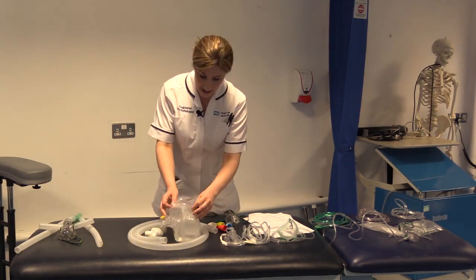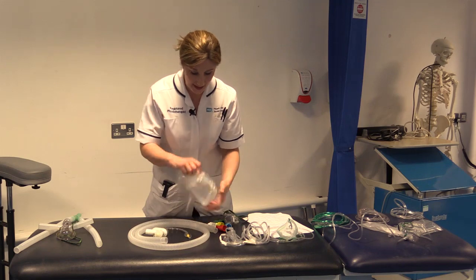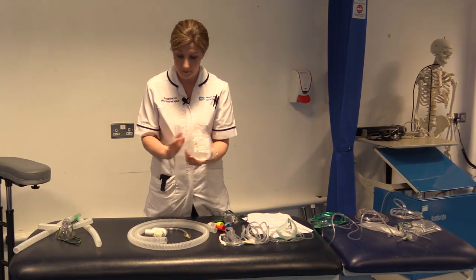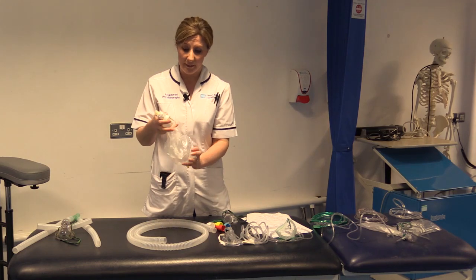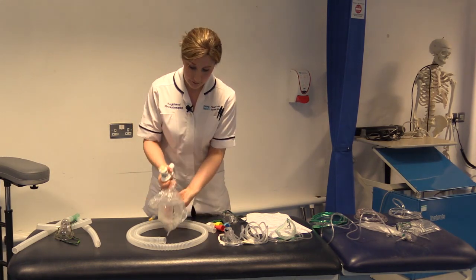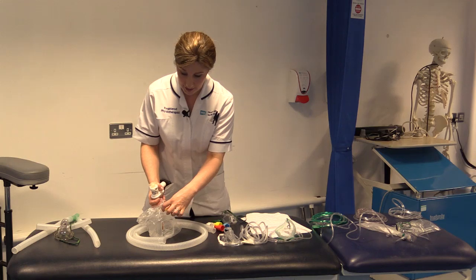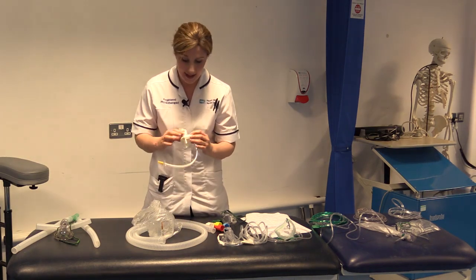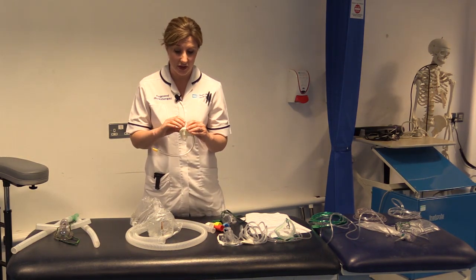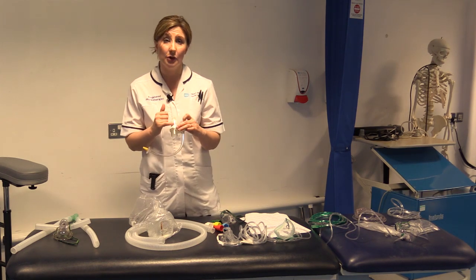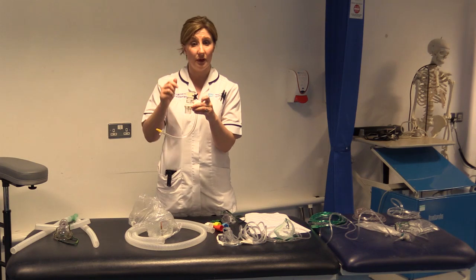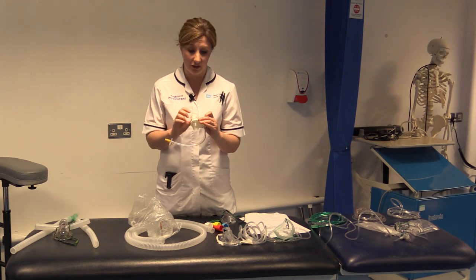So this is the setup here where you would expect to see the water. And you have this device which would screw in here, pierced at the front when you've removed the sharps cover in through here, and then you're going to select which concentration of oxygen you want. And this little device will guide you as to the minimum flow rate that you need to turn this up to on the wall to achieve that concentration of oxygen.